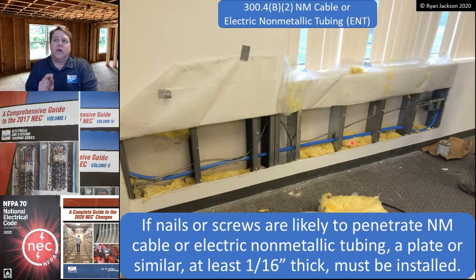300.4(B)(2) talks about not only NM cable, but also electrical nonmetallic tubing, or ENT, Smurf tube as some people call it. If nails or screws are likely to penetrate NM cable or ENT, a plate or similar, at least 1/16 inch thick, must be installed. Now, this is for metal stud framing. Only applies to NM cable and ENT. It does not apply to MC cable or any raceways other than ENT.